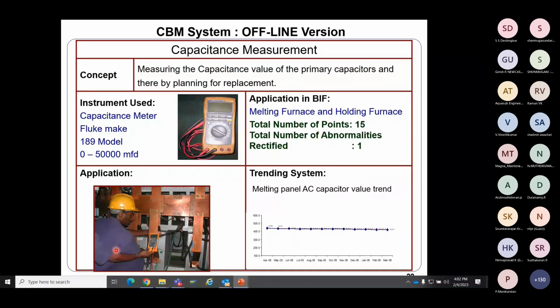Capacitance measurement: I've already explained the various capacitor banks connected with the melting system, where people can physically see if a capacitor is bulging or oozing oil or electrolyte, but you can also measure it. When doing such measurements, you must be sure the system is completely off and properly earthed. Without earthing, taking capacitor measurements might endanger the safety of personnel and property. So before getting into such advanced measurements, revisit the first points I talked about: know the machine in detail. Then you can get into any activity, because overconfidence leads to accidents. You must be very careful about that.